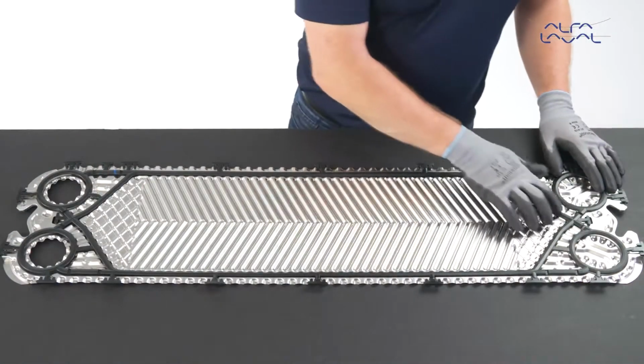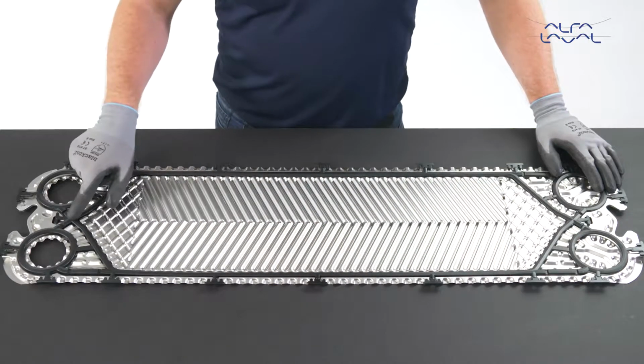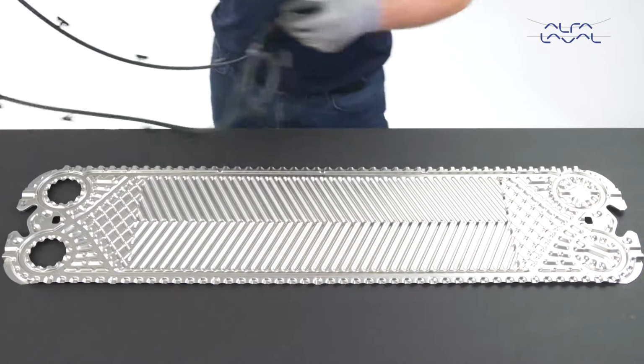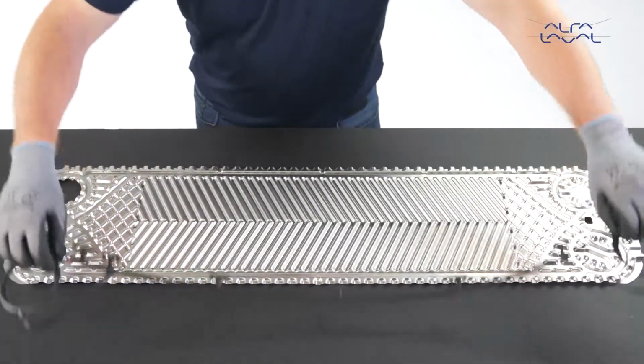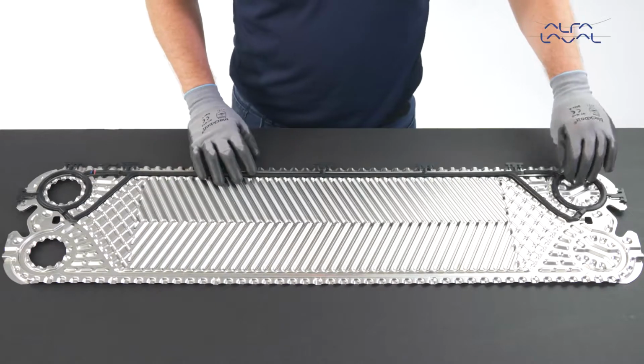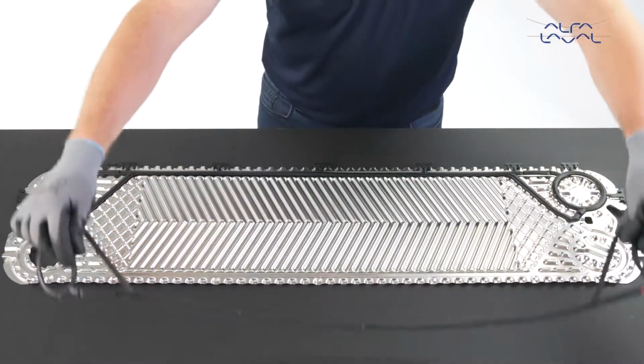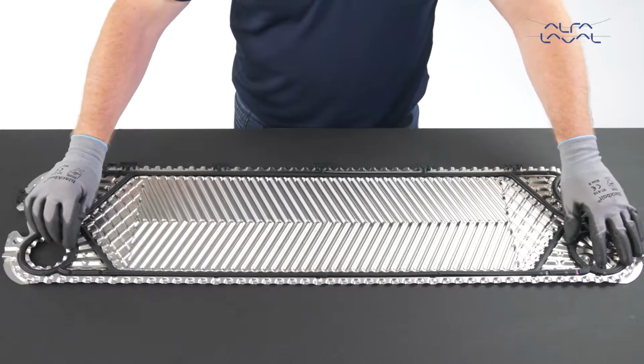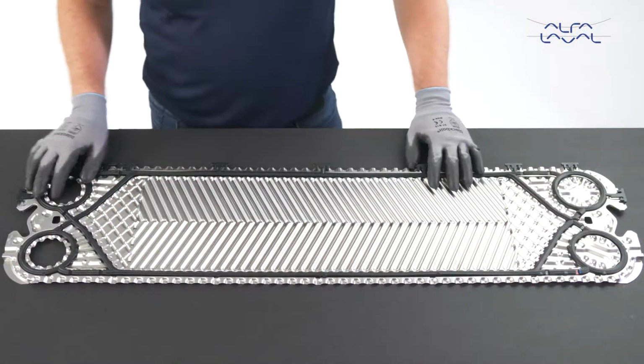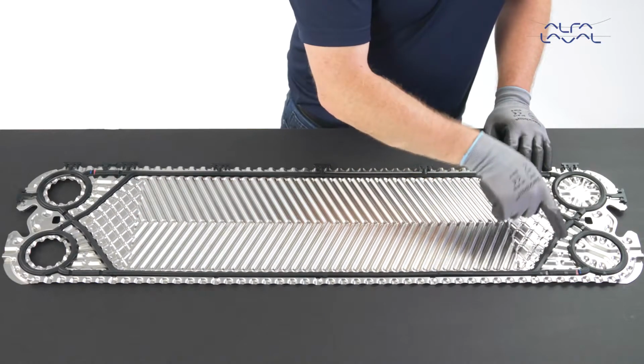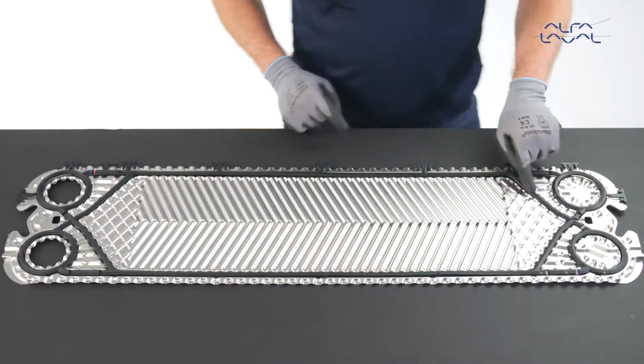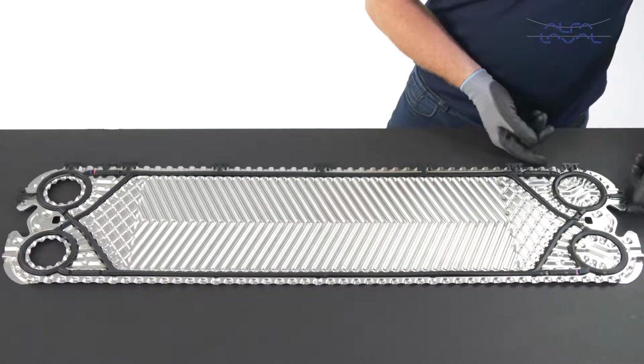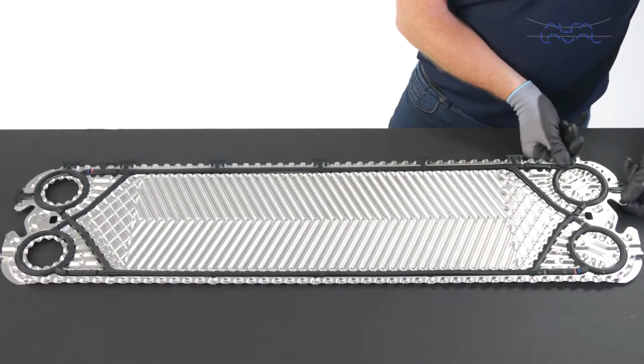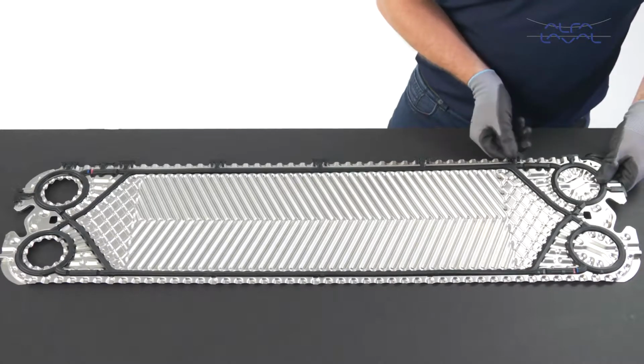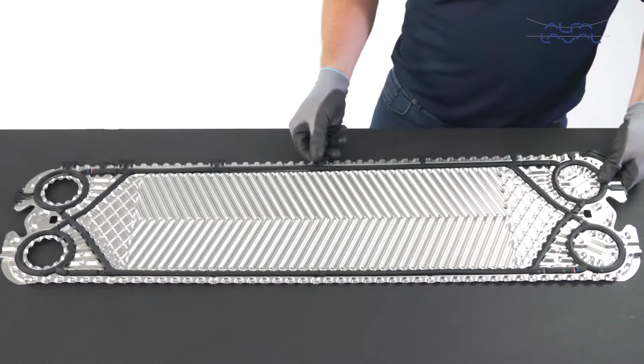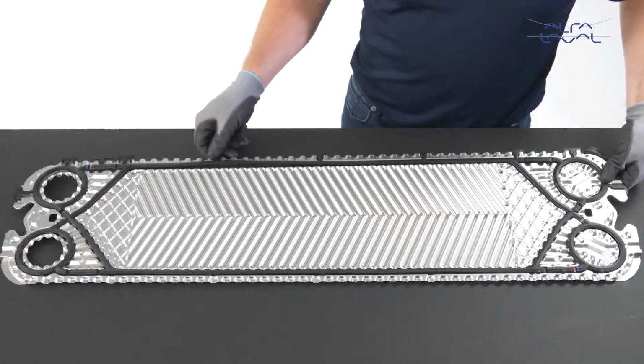There is a designated gasket for end plate 2 plates. However, if the end plate 2 gasket is not available, it is possible to make one by using 2 regular channel plate gaskets. Cut the 2 channel plate gaskets in half. Use the 2 pieces with complete ring gaskets. The clips and connection beams must be removed on one of the halves. Tape the 2 halves of the gaskets that you cut together. We recommend that you use GC1 double adhesive tape. Remember, do not put any glue or tape in the ring gasket areas.